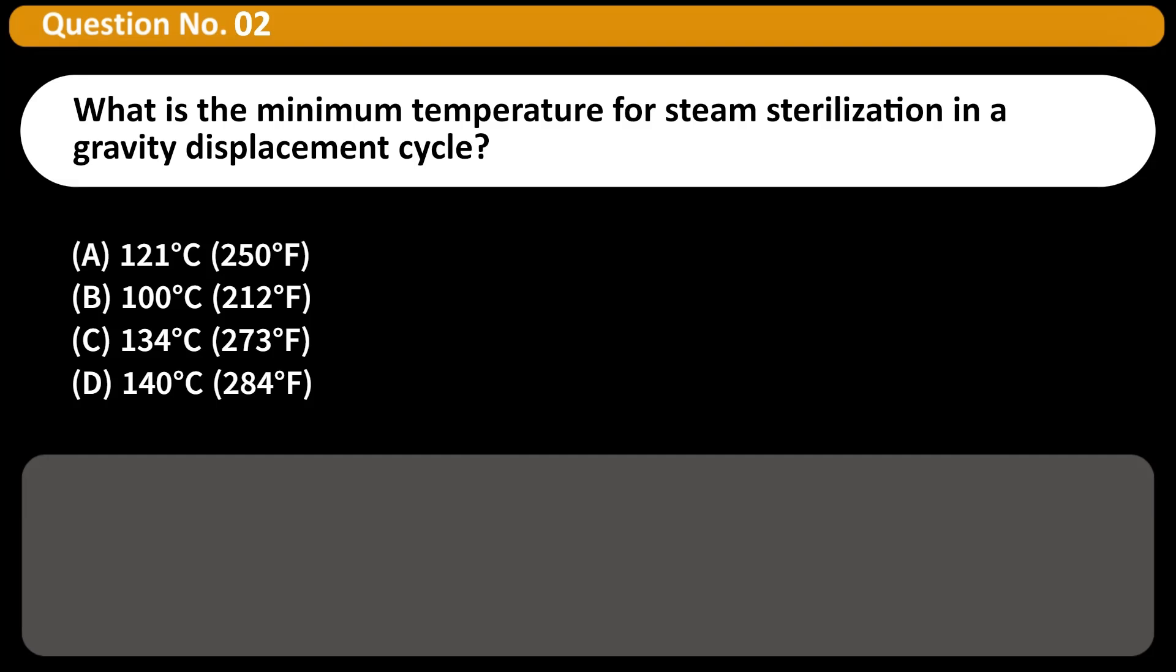What is the minimum temperature for steam sterilization in a gravity displacement cycle? A. 121 degrees Celsius (250 degrees Fahrenheit), B. 100 degrees Celsius (212 degrees Fahrenheit), C. 134 degrees Celsius (273 degrees Fahrenheit), D. 140 degrees Celsius (284 degrees Fahrenheit). Answer A. The standard temperature for gravity steam sterilization is 121 degrees Celsius or 250 degrees Fahrenheit.